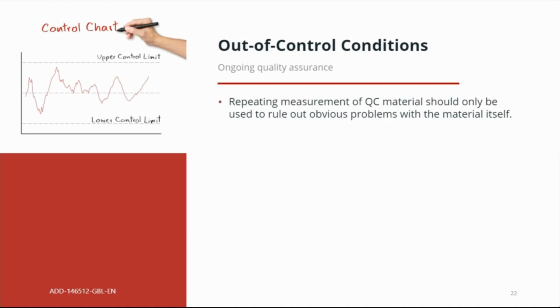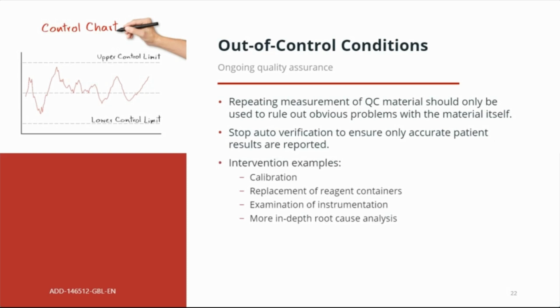When we have an out-of-control condition, this means an intervention is needed. So our troubleshooting begins. Repeating measurement of QC material should only be used to rule out obvious problems with the material itself. We would stop auto-verification where that is in place to ensure that only accurate patient results are reported. And then our intervention examples could be calibration. It could be replacement of reagent containers, examination of our instrumentation, and then more in-depth root cause analysis if we're still not sure. Once those corrective actions are executed, QC is repeated, we verify the restoration of in-control condition, and then it's also important to look back to the last time the control results were acceptable and ensure prior results remain accurate.